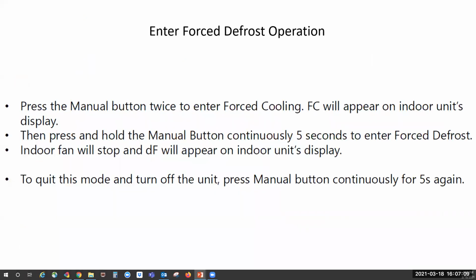Not all units are capable of forced defrost. You want to check with your service manual to make certain. If they are, they'll have a manual button, and you'll push it twice to enter force cooling. An FC will appear on the indoor unit's display. Press and hold the manual button for 5 seconds to enter force defrost. Your indoor fan will stop, and DF will appear on the indoor unit display. To quit the force defrost, you just push the manual button continuously again for 5 seconds.